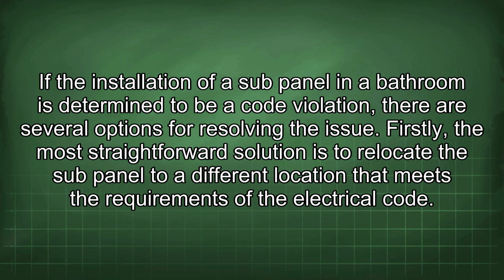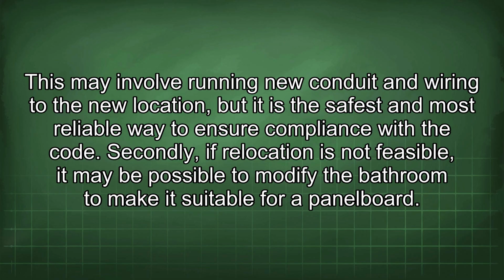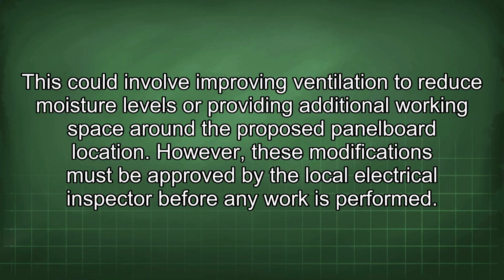Firstly, the most straightforward solution is to relocate the sub-panel to a different location that meets the requirements of the electrical code. This may involve running new conduit and wiring to the new location, but it is the safest and most reliable way to ensure compliance with the code. Secondly, if relocation is not feasible, it may be possible to modify the bathroom to make it suitable for a panel board. This could involve improving ventilation to reduce moisture levels or providing additional working space around the proposed panel board location. However, these modifications must be approved by the local electrical inspector before any work is performed.